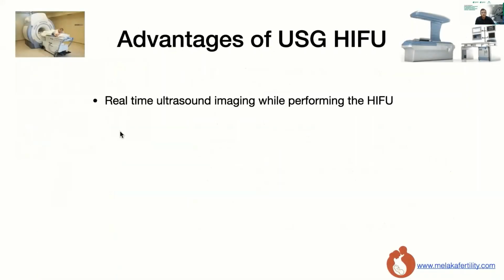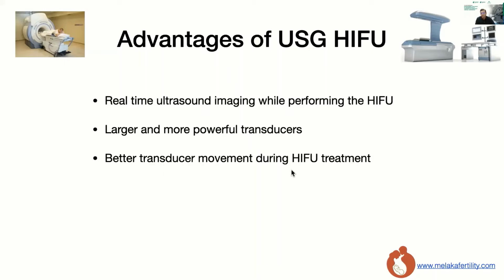So what are the advantages of ultrasound-based HIFU? From what I told you, firstly, ultrasound-based HIFU has real-time imaging when we perform the HIFU, as opposed to MRI-based HIFU, which is not real-time. That means I'm actually looking at the uterus in real time while I'm shooting, and I can see where exactly the shot is. That is a big advantage of ultrasound-based HIFU. Also, as I showed earlier, the transducers are more powerful and larger, and there's better transducer movement. The transducer can move about 12 centimeters on either side, front and back, and also up and down.